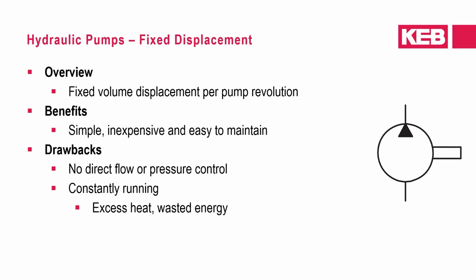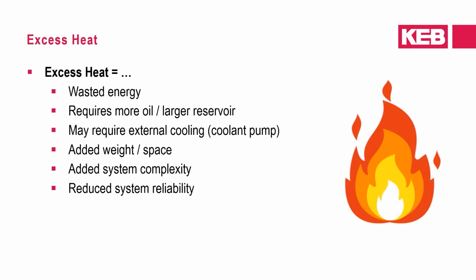When the pump is running, the fluid is flowing, which creates friction resulting in heat. The flow also builds pressure and when not put to use, is dissipated at maximum pressure by a relief valve, resulting in wasted energy. Whereas the flow is not directly controlled by the speed of the pump, it can be controlled with flow control valves, but these represent a resistance to fluid flow, which also creates heat. In regards to excess heat, there are several ramifications. The excess heat not only represents wasted energy, but also means more oil and a larger reservoir would be needed to mitigate oil heating and possibly external cooling. These add weight and take up space on the vehicle, as well as add to the system complexity, which reduces system reliability.